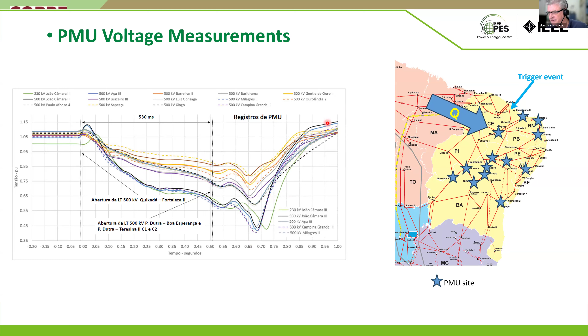Okay, this is the second problem. The first problem I already talked about was that unfaulted line that tripped. The second problem was this line here, P. Dutra – Boa Esperança. Before the problem, this line was carrying 1300 amps. In half a second it jumped up to 2100 because of the Q. This is basically reactive current. And then it turned off because the second problem was out-of-step protection. You see here the impedance plot in one of the lines, and the out-of-step protection tripped these 3 lines here that you see with the stars.